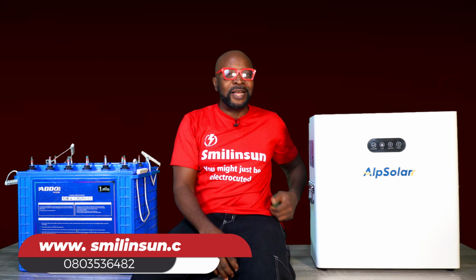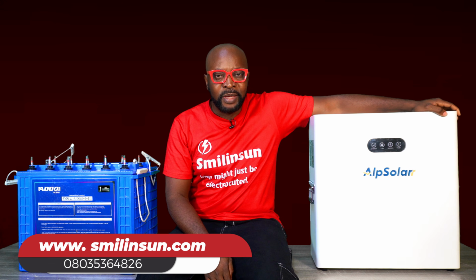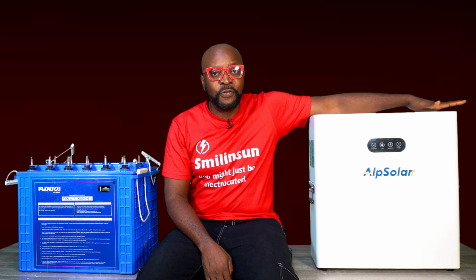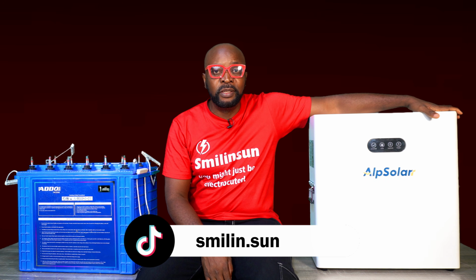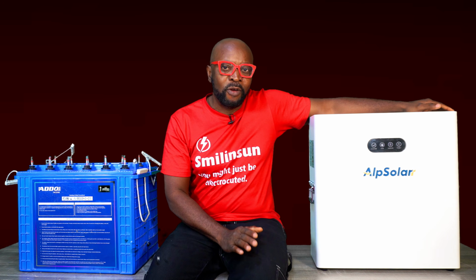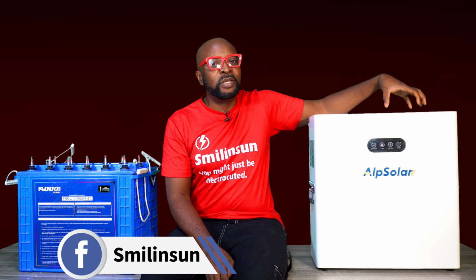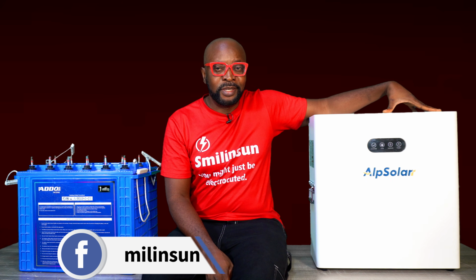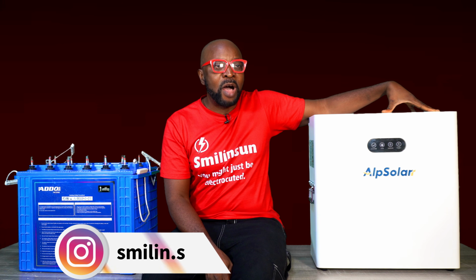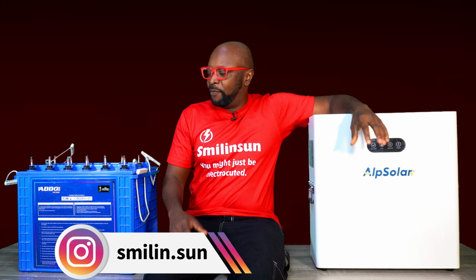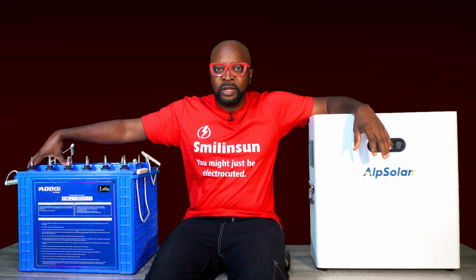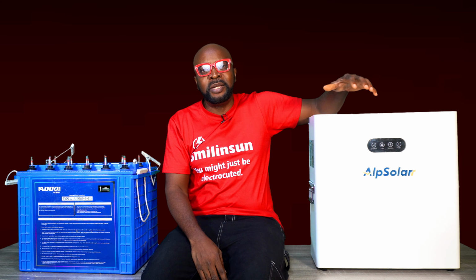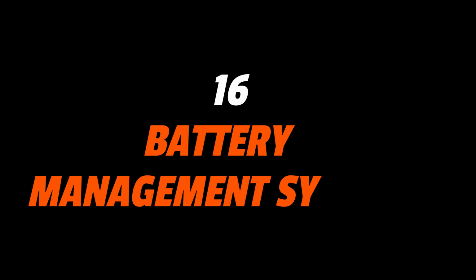But for the lithium battery, unfortunately, it's not the same case. The lithium battery is going to fail with no warning. When it gets to the end of its life cycle, it is suddenly going to fail. It is barely going to be holding any power at all. So that's their behavior. The tubular battery is going to give you ample time to get a new battery, but unfortunately the lithium battery won't.